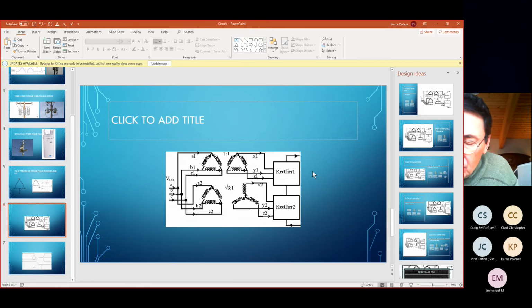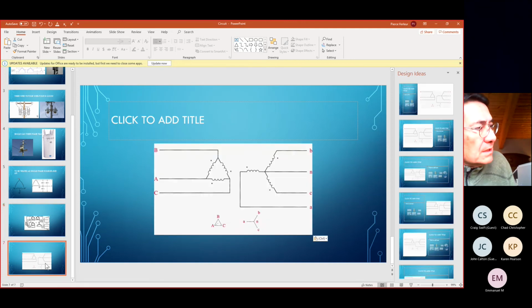I realize that there's design modes for new construction, in which case you can reasonably assume, although assuming is always dangerous, that the configuration will be the desirable delta Y with the center tap grounded. Verifying that is important. If you are going into existing installations, especially in rural areas, please check and make sure. Because as you've seen today, the equipment and the cost associated with that equipment, let alone the consequences of not having correct configurations, can be significant.